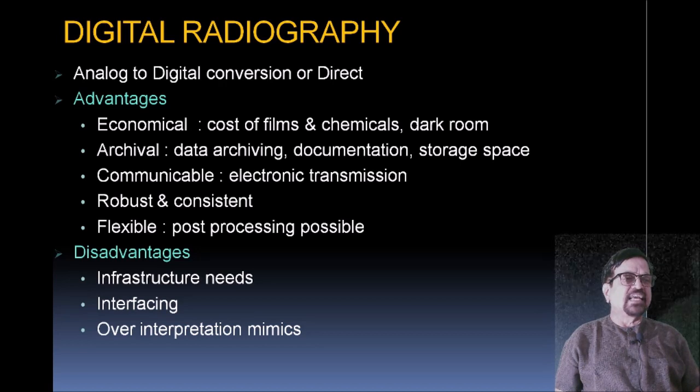Now, the disadvantage is the infrastructure need. Earlier, whichever department had conventional radiology with a darkroom, that darkroom needs to be removed, and we have to set up a different room for this CR system. Then interfacing and over-interpretation mimics. What does it mean? A lot of things in CR, that is computerized radiography, depend on the settings. So if a setting is done wrongly, there can be different or over-reporting, or some details can be obscured or may not be visible. So the operator at the console has extreme importance.